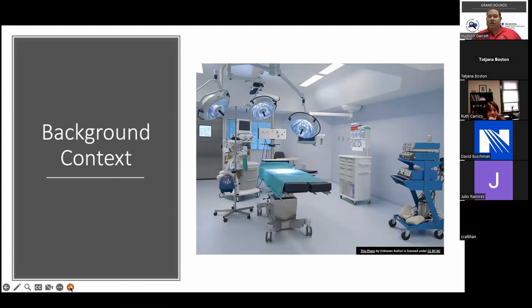When we think about this in terms of medical devices, we've got to know where the device is intended to be used - that intended use. Then according to the Spaulding classification, that tells us how to reprocess it. Those levels of reprocessing can vary by type and honestly by where we use it in a facility. Even with the same pieces of equipment, you may have differing opinions related to different service lines.